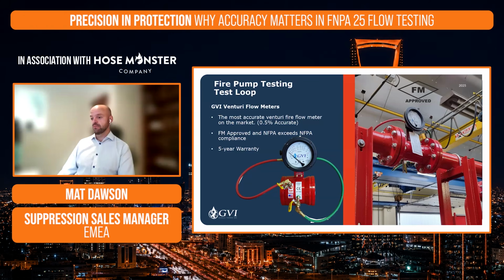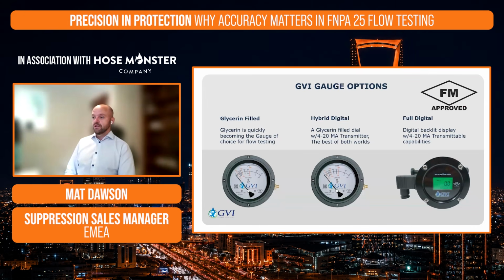On this meter here, you can see the red hose is the high pressure, and the green hose is the low pressure. And we're basically using the Venturi principle to measure flow. With our GVI gauges, we've got some different options. So on the one we just saw, that was our standard gauge. We are seeing a lot more people tend to go for the glycerin filled.